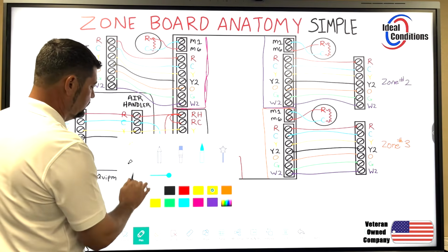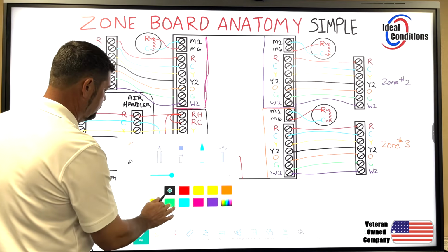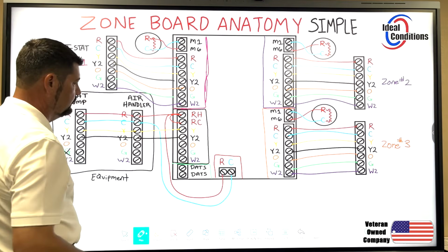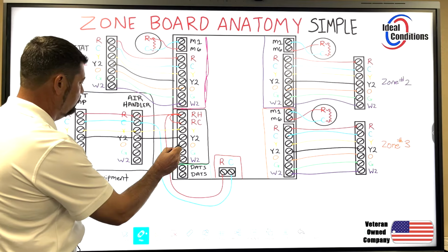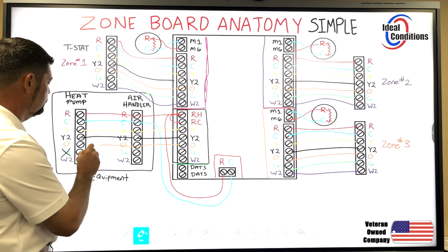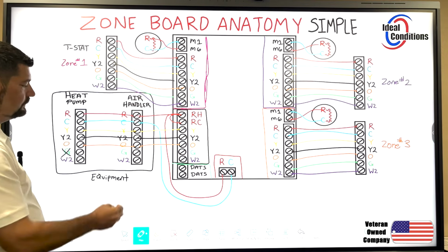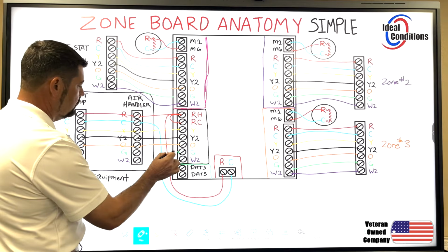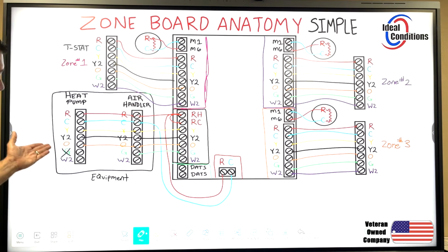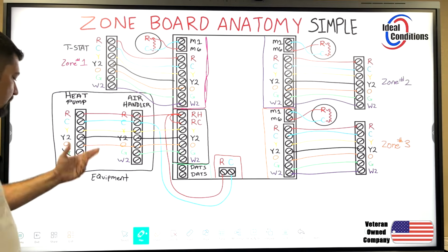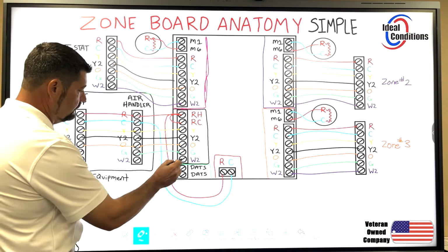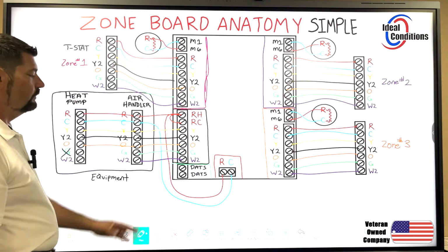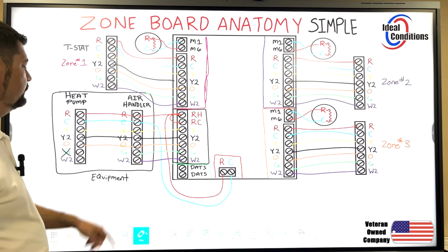Next colors are orange and green for fan. O comes out from here, going out to the heat pump condenser, and we have our G call here, though there's no G call from the condenser. Finally, we land W2 from the equipment side of the zone board over to the air handler.